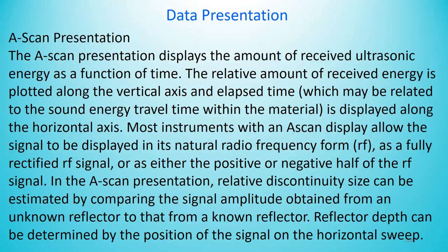Data presentation. A-scan presentation displays the amount of received ultrasonic energy as a function of time. The relative amount of received energy is plotted along the vertical axis and elapsed time along the horizontal axis. Most instruments with an A-scan display allow the signal to be displayed in its natural radio frequency (RF) form, as a fully rectified RF signal, or as either the positive or negative half of the RF signal.